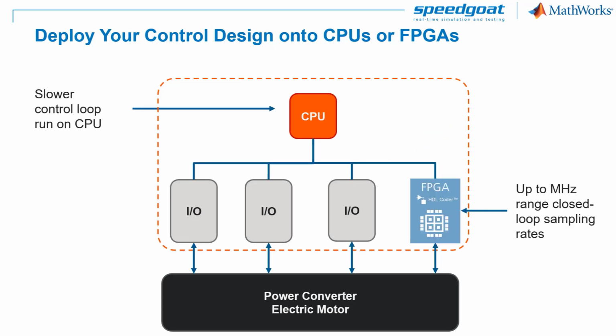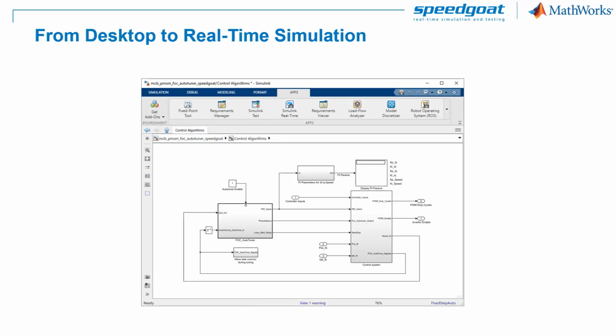There is the possibility to execute the fast closed-loop control algorithm in the FPGA. We still use the CPU for slower components of the control design, but we can generate HDL code, synthesize, and run the hardware implementation in the FPGA. That's typically much faster as we exclude the CPU-FPGA communication time at every sample step. That way, the control algorithm can directly talk with the inputs and outputs.